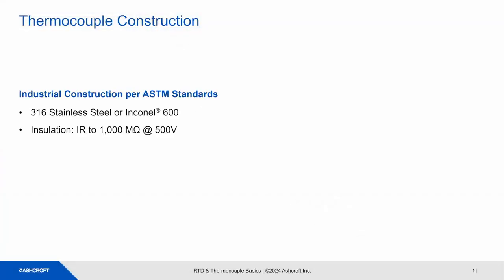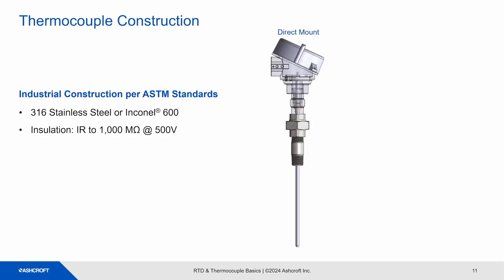Thermocouple construction. Thermocouple probes are made to ASTM standards. Sheath materials are 316 stainless steel or Inconel 600. They have a high insulation resistance of 1,000 megohms at 500 volts. There are direct mount probes. The thermocouple sensor is at the tip of the probe. They use mineral insulated or MI cables. They have a customer specified lag. The most common shown is the nipple union nipple lag. They have an electrical junction box or head directly mounted on the probe.